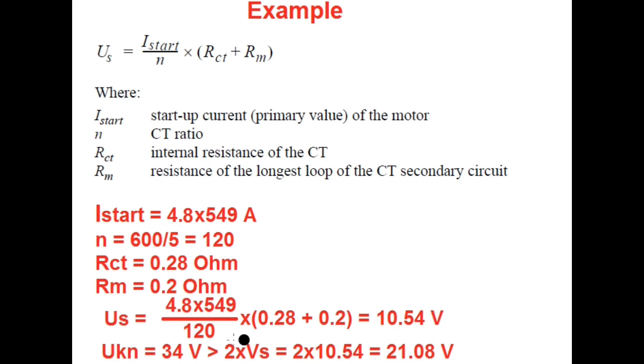We check whether the knee point voltage is greater than two times the stabilizing voltage. The knee point voltage is 34 V, which is greater than 2 × 10.54 = 21.08 V. Therefore the CT requirement is fulfilled.